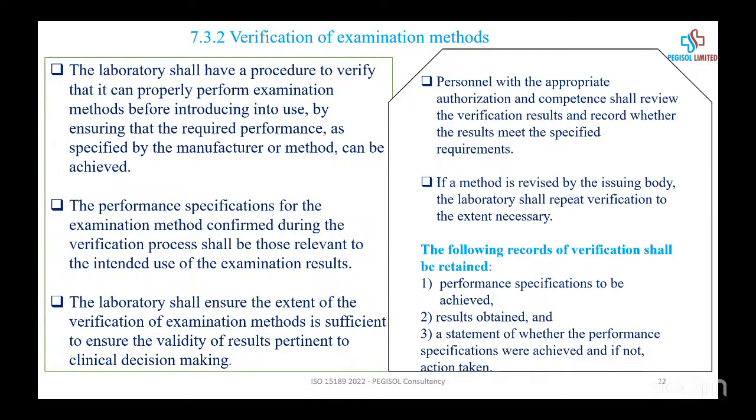We use it to run the test for maybe 10 runs or thereabout. Then we calculate the precision, the accuracy, bias, and so on, and find out if it's in agreement with what we have in the product inserts.